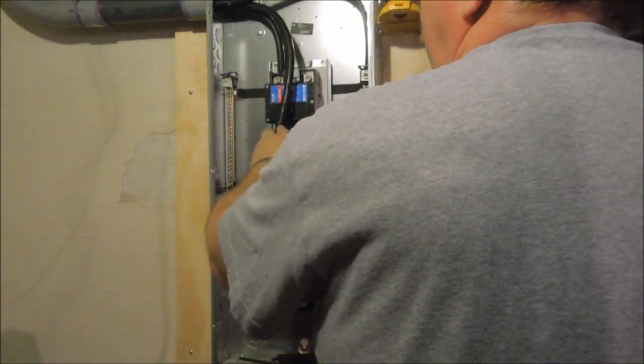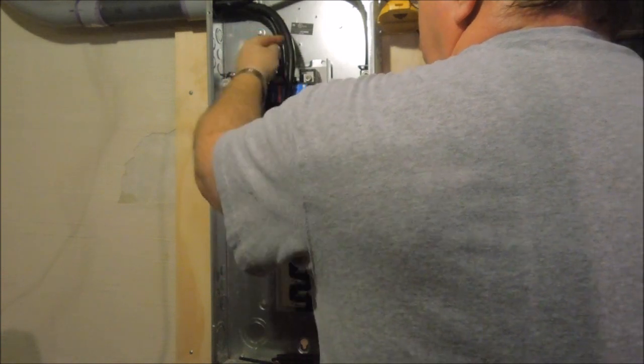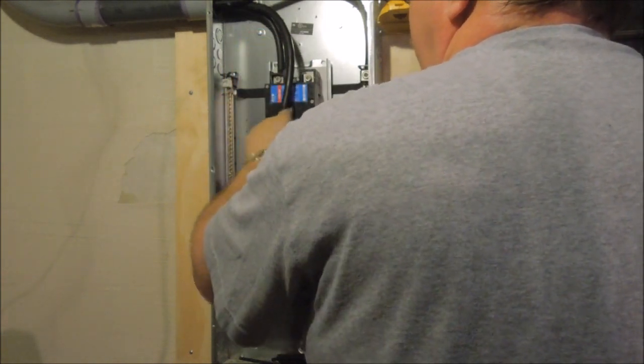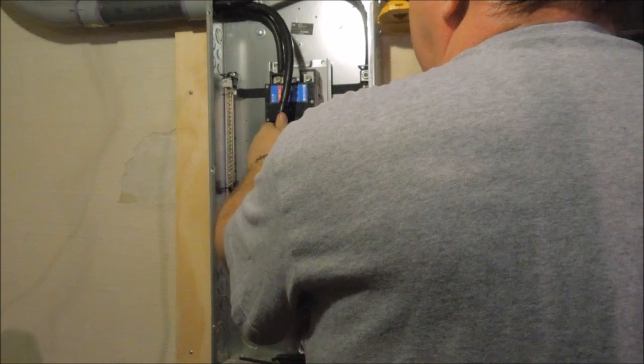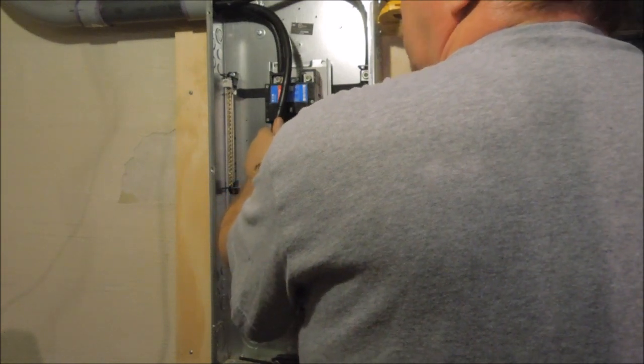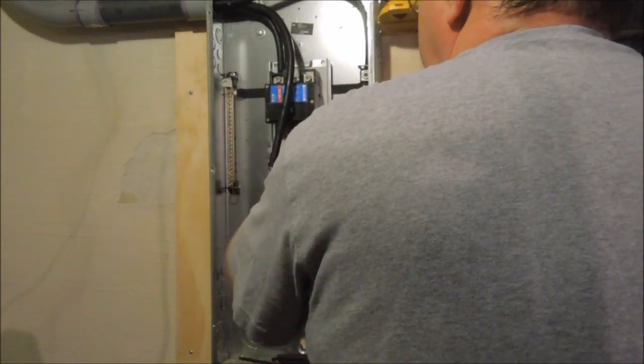We wanted to make sure we had a little extra because if you end up short you can't add anything to this wire. You can't splice it. It has to be a continuous run from the meter box to the panel.